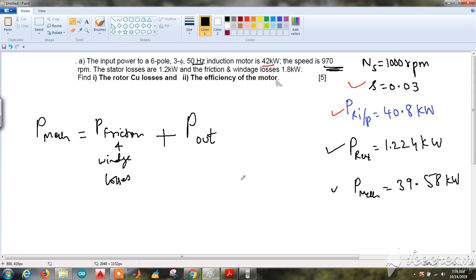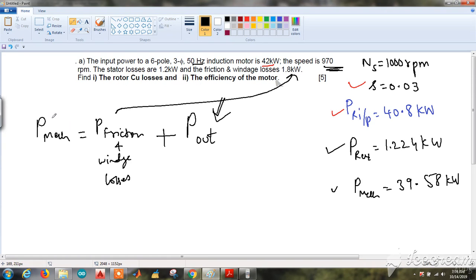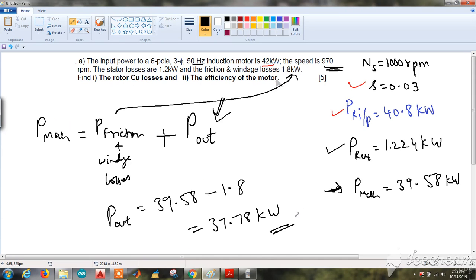The mechanical power delivered to the rotor equals friction and windage losses plus the output power. The friction and windage losses are given as 1.8 kW, and we have found P_mechanical = 39.58 kW. Substituting, the output power P_out = 39.58 − 1.8 = 37.78 kW. We have also confirmed the rotor copper losses as 1.224 kW.